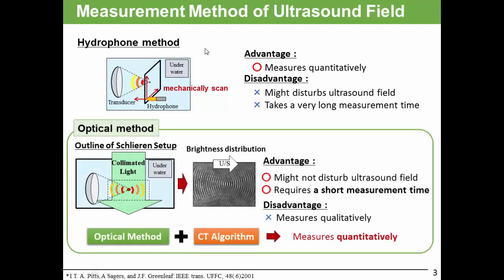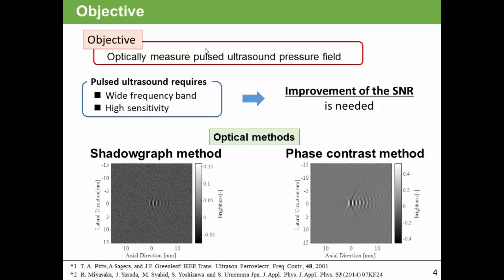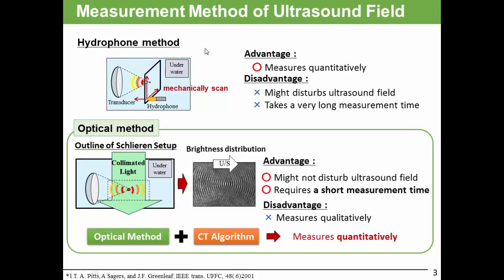Let me explain the measurement method of ultrasound field. The conventional way to measure the ultrasound field is using hydrophone method. The advantage of hydrophone method is to measure quantitatively. However, hydrophone method might disturb ultrasound field and takes a very long measurement time.